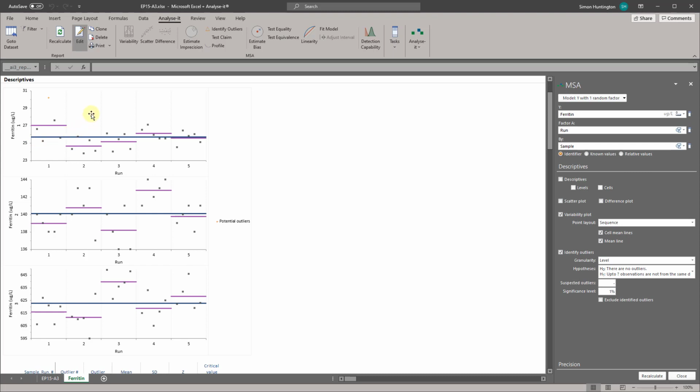You should observe the scatter of the points to ensure there are no obvious problems. If a result appears spurious, then you should investigate and correct any mistakes. If the data appears to be unusable, stop the evaluation and begin an expanded evaluation of the sources of measurement error, or contact the manufacturer.